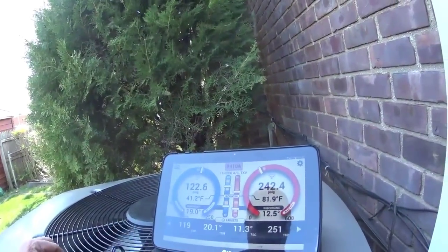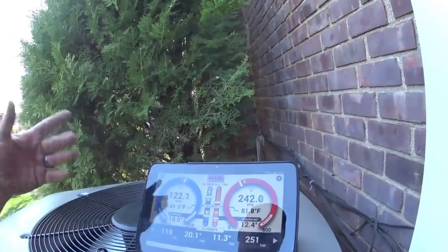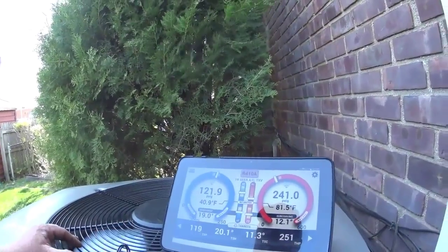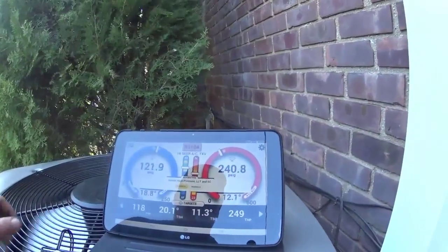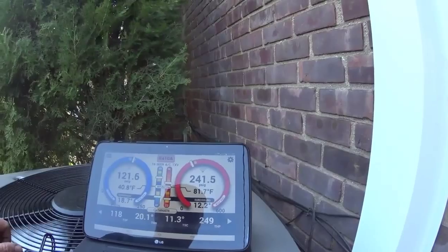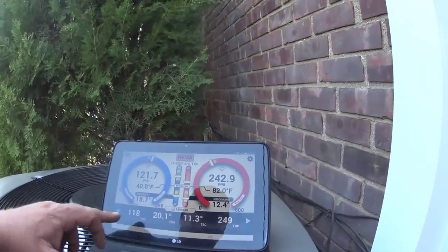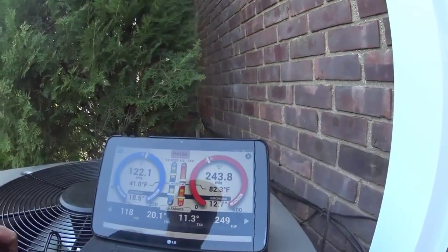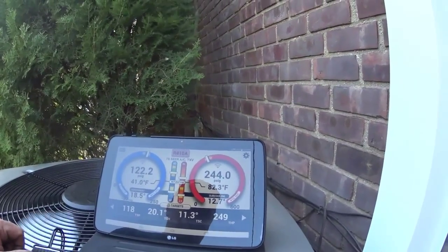So this is my system — it's a three-ton Lennox XC14 matched with a CBX27 air handler, which is giving me a SEER rating of 16.2. That's what I have for every profile. We're doing pretty good — we're pretty much spot on with our pressures. The superheat is off a little, subcooling off a tiny bit — it was hanging around 11.5 before so I'm pretty happy.